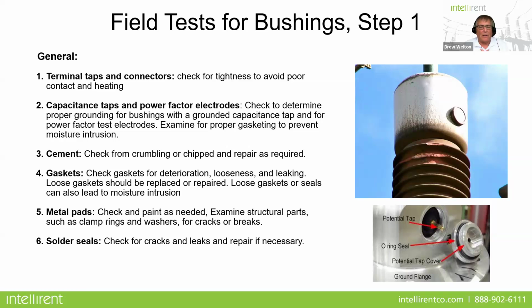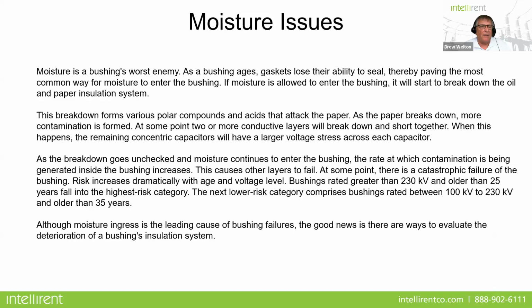But gaskets is a big thing. And the one thing I do want to say about leaking gaskets, if you see oil coming out of the gasket of a bushing, you can darn well guarantee that moisture is going in. Anywhere you have oil leaking out of the transformer, moisture is getting in, and you could very well have a moisture issue. So your metal pads, check and paint as needed. Examine structural parts such as clamp rings and washers. Look for cracks and breaks, and any solder seals. Check for cracks and repair if necessary.